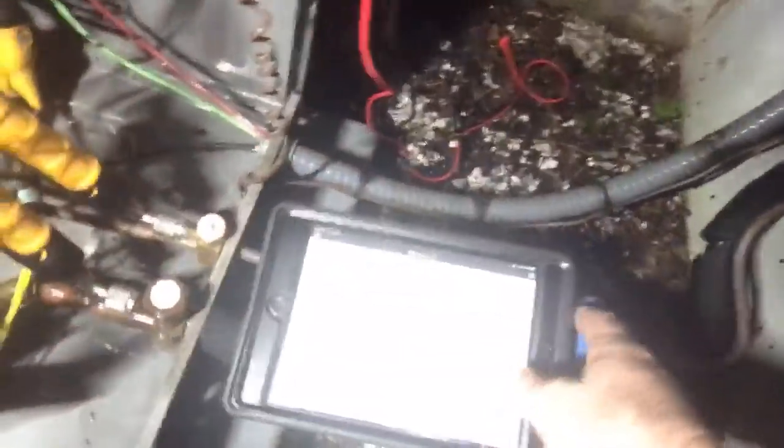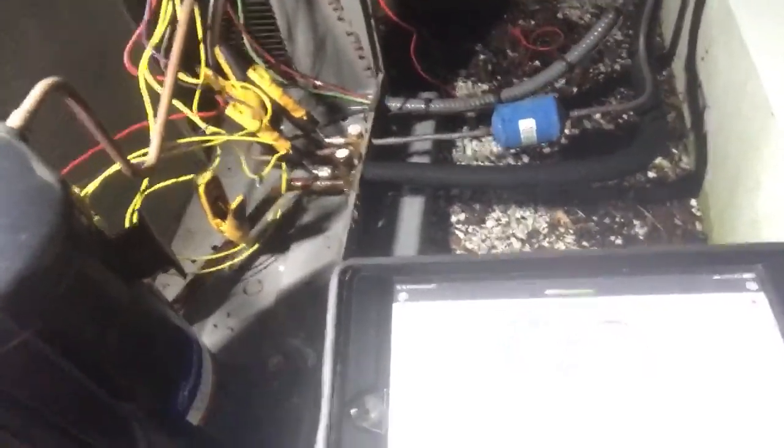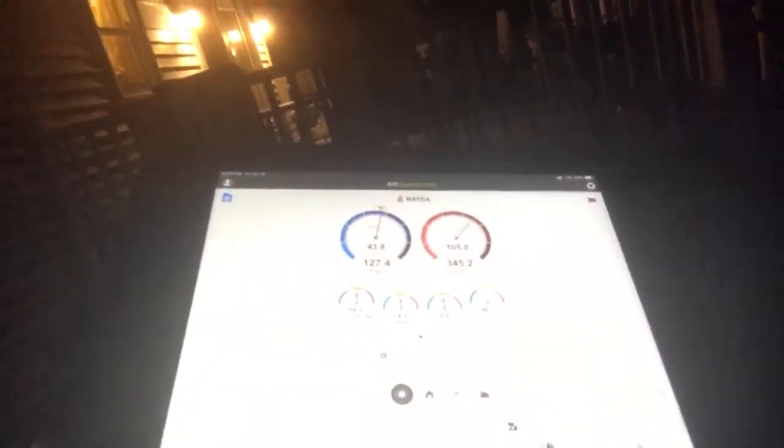Let's see — I put it here and you can get your superheat and sub-cool. Superheat is off — wonder why, let me go check that probe out. I'm not getting any sub-cool, I have none. No pressure. Now that connected. My machine is operating right now at almost 10 degrees of sub-cool and 14.6 degrees of superheat.